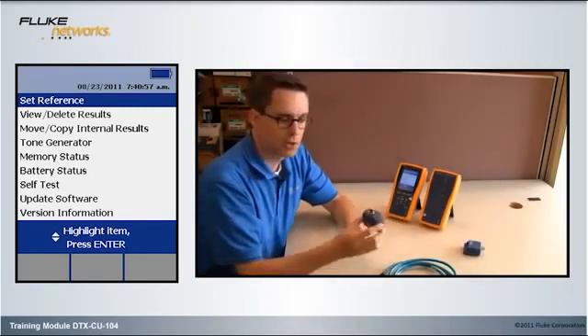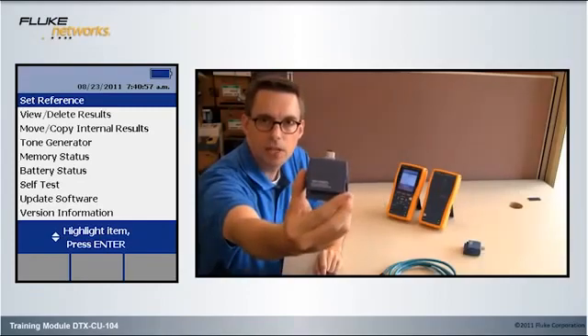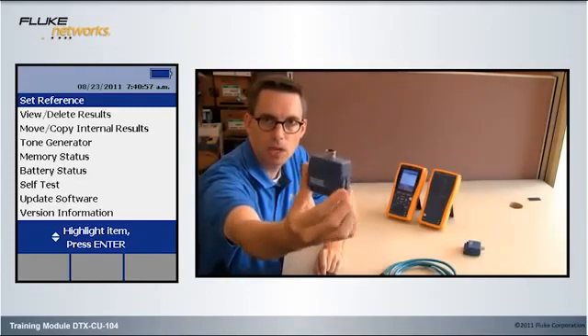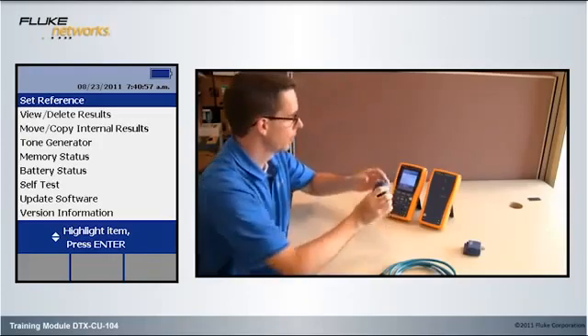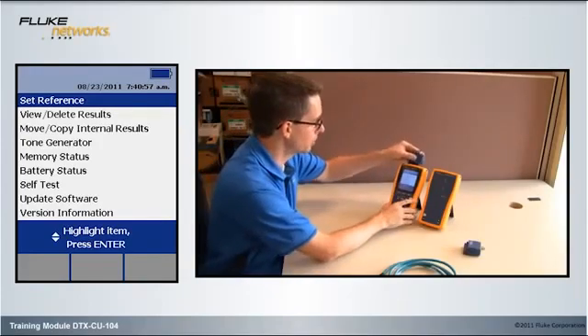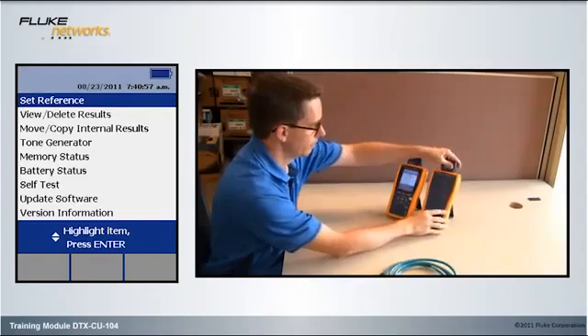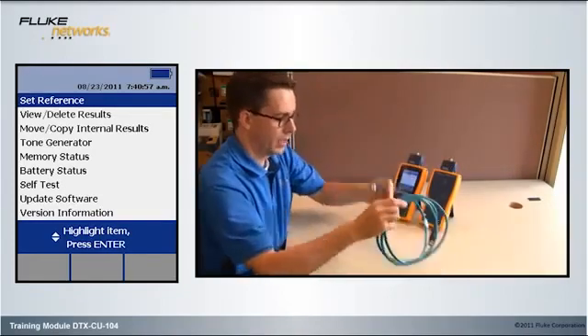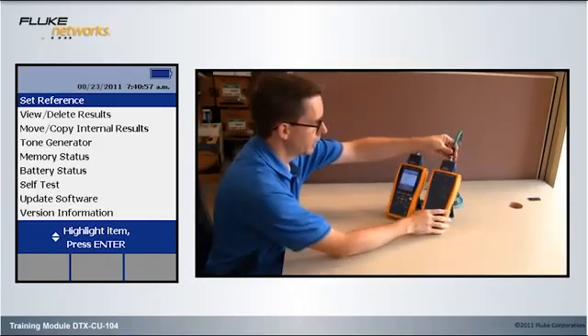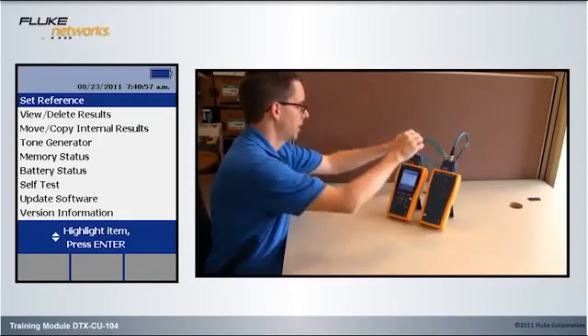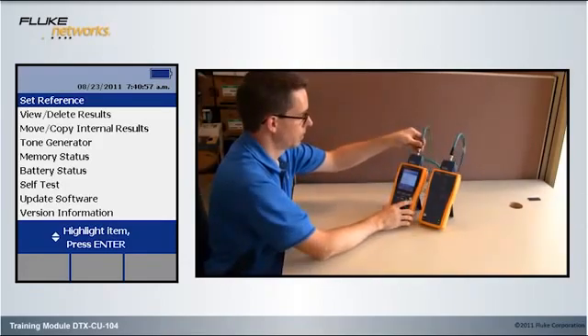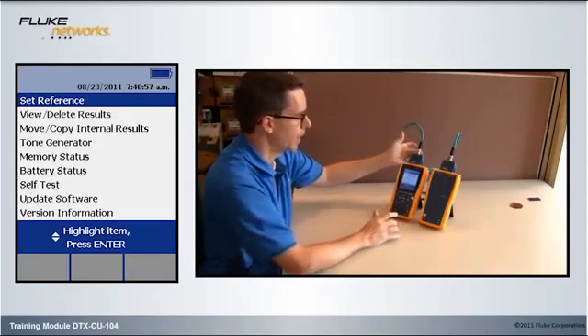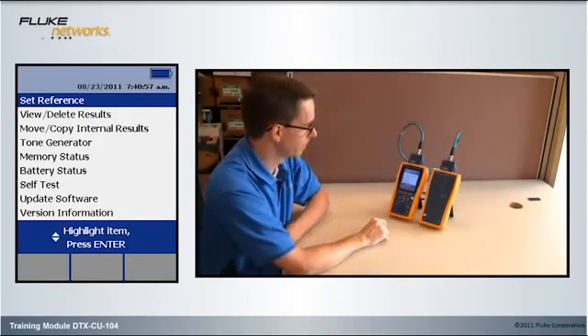Fluke and Fluke Networks offers these DTX-021 adapters, which have the M12 connector in the top, which is going to allow us to do the patch cord certification. The M12 is keyed, so we need to very carefully find the key and place it on there. Same on the main unit as well. I don't need to screw these in, not for the purpose of certification.